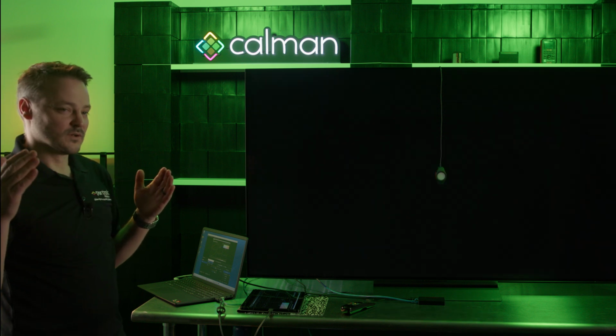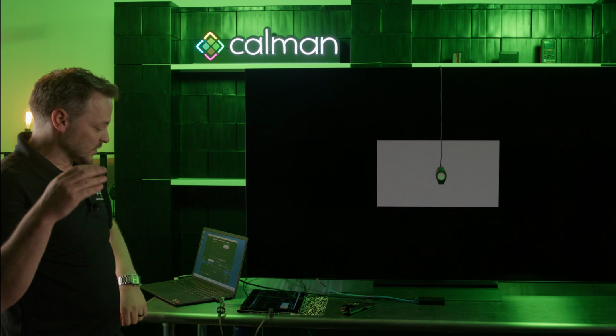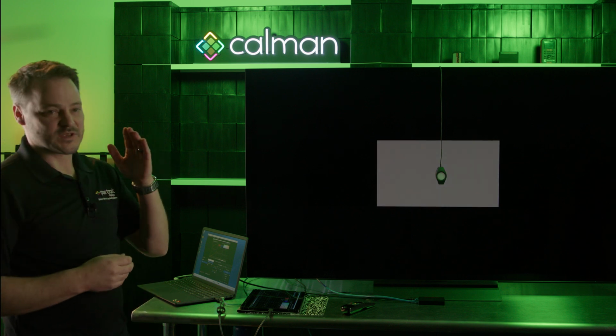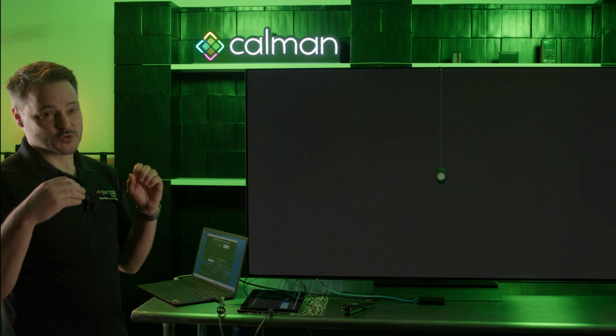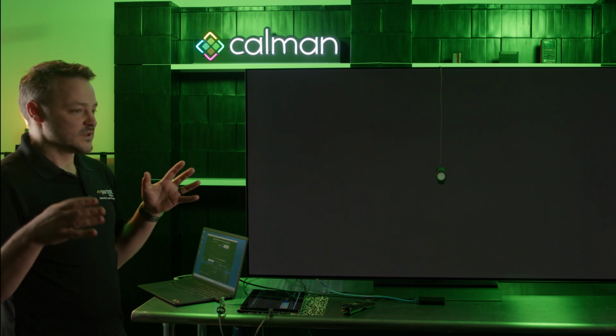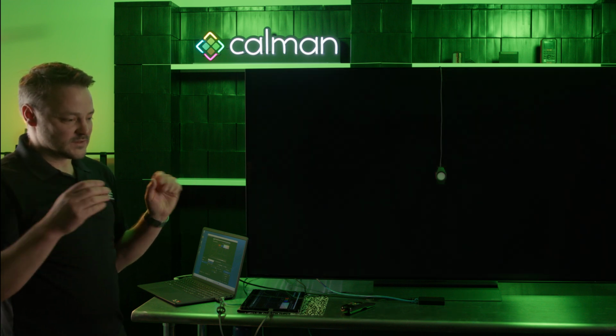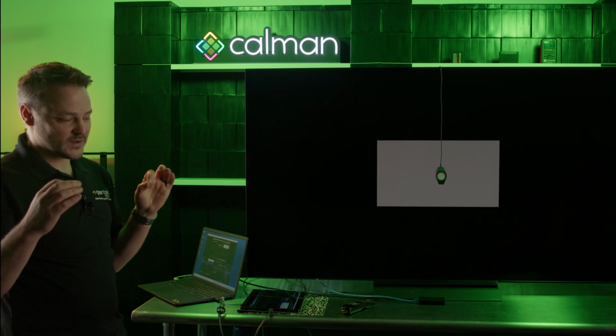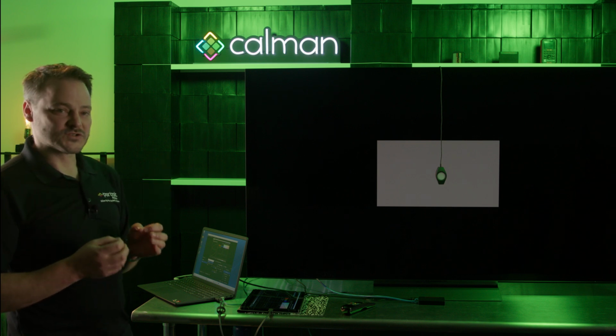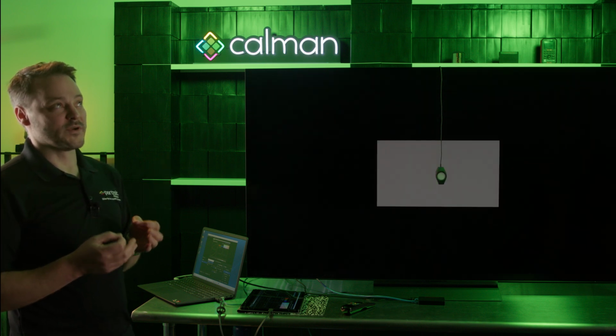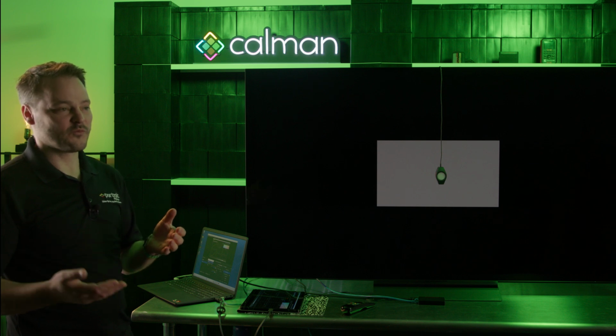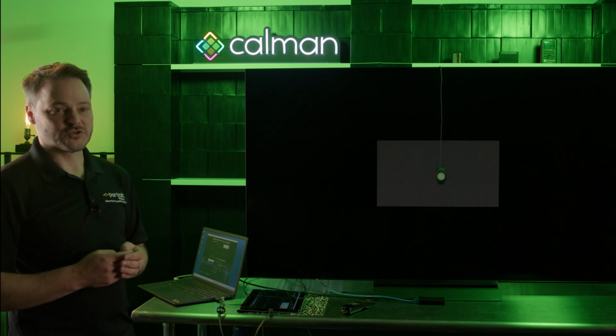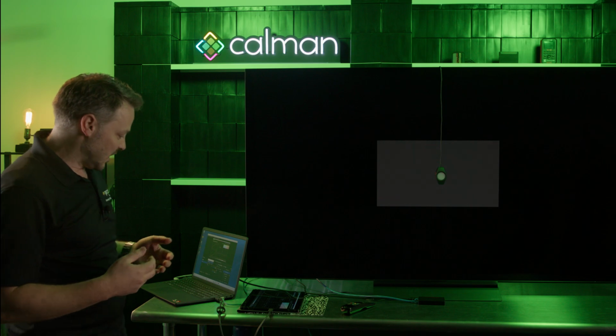We're going to measure the full grayscale. We're going to start by measuring at 100. Then we're going to skip down to 50. Then we're going to measure 25 and 75%. And the reason that we do that is we're going to measure each point, and we're going to adjust at each point, but we're also going to pre-adjust some of those points first, so that hopefully as we go through, that calibration is going to go more quickly.